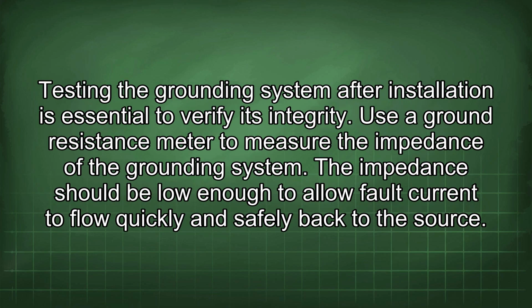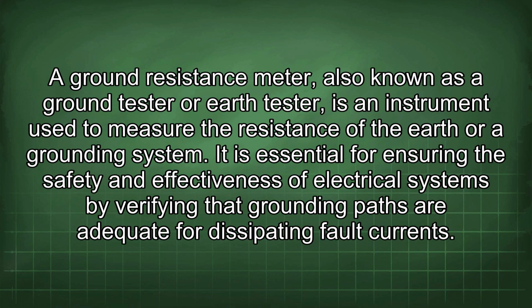Testing the grounding system after installation is essential to verify its integrity. Use a ground resistance meter to measure the impedance of the grounding system. The impedance should be low enough to allow fault current to flow quickly and safely back to the source. A ground resistance meter, also known as a ground tester or earth tester, is an instrument used to measure the resistance of the earth or grounding system. It is essential for ensuring the safety and effectiveness of electrical systems by verifying that grounding paths are adequate for dissipating fault currents.